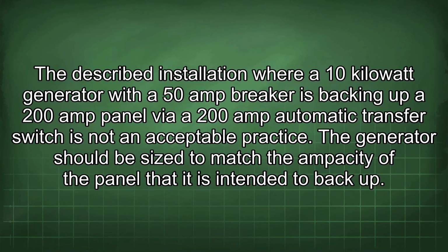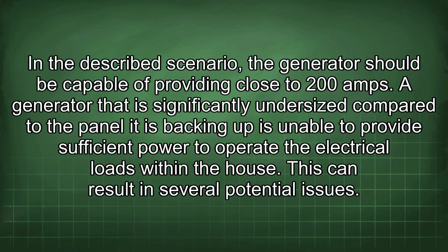The described installation, where a 10 kilowatt generator with a 50 amp breaker is backing up a 200 amp panel via a 200 amp automatic transfer switch, is not an acceptable practice. The generator should be sized to match the ampacity of the panel that it is intended to back up. In the described scenario, the generator should be capable of providing close to 200 amps.